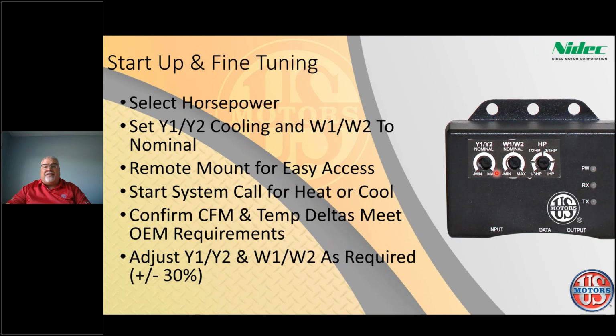So once we've got these installed, we're going to remote mount this. Honestly, on the ones I've done, I've basically run that wiring out and closed that lower door panel, because I want to make sure when I check my airflow and make sure I'm getting enough, that I'm not giving too much negative pressure by having that door panel open. So close that thing up, and then we're going to call for heat or call for cool. I would suggest using whichever season we're in. Right now would be cool, right? So I'm going to check my airflow and temperature deltas, and I have a 30% up and a 30% down ability to dial this system in.